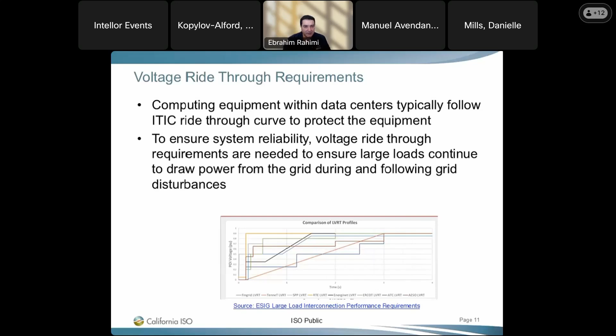One aspect is post-fault active power recovery. When a severe fault happens, obviously any equipment cannot continue to operate normally, so large load is allowed to reduce their power consumption depending on the severity of the fault. However, when the fault is cleared and voltage returns to normal, there needs to be some requirement that the power consumption from the grid should recover to close to pre-disturbance levels within a given time. This will be discussed later, but that's one of the aspects the team is working on - what should be the requirement for the CAISO system.